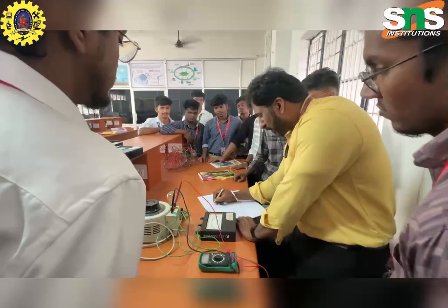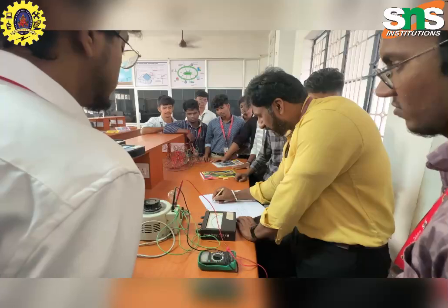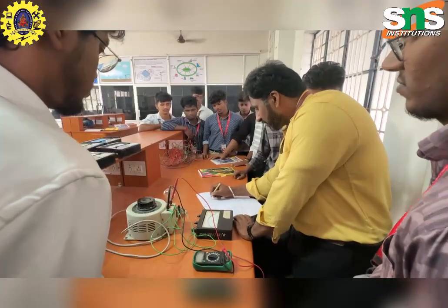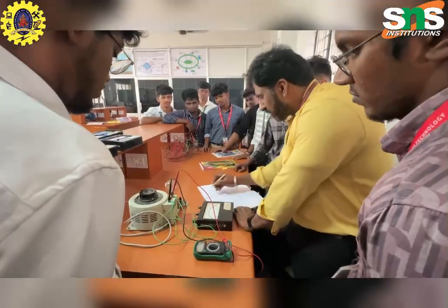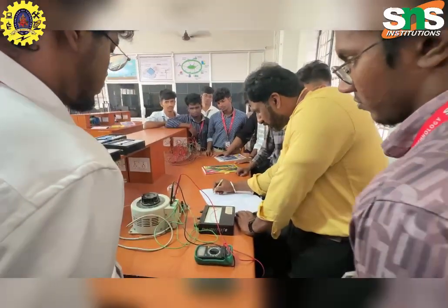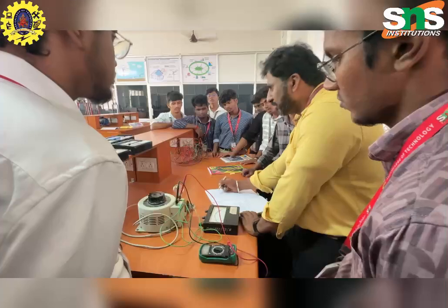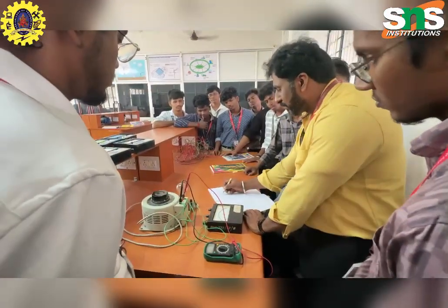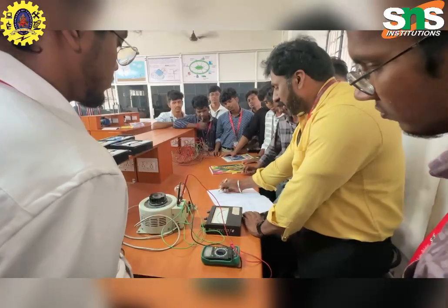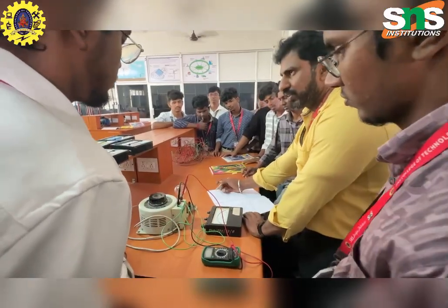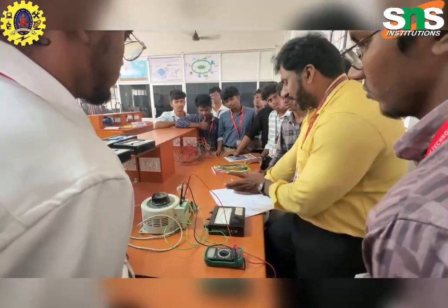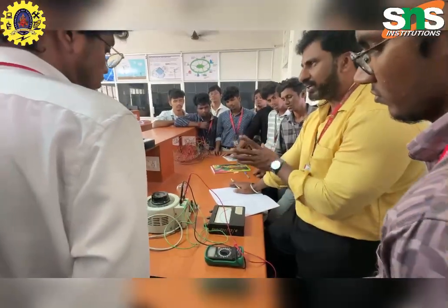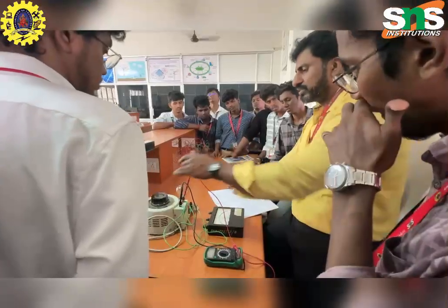So I have a supply voltage, and directly connected to it is one voltmeter. This voltmeter will be the standard one, a multimeter. The next voltmeter is the test meter, or measuring meter. When we switch on the supply, the standard meter will show one value and the test meter will show another value. So we have different values. When directly connected to the supply, we can take only one reading, but we need more than 5 readings. That's why we are using a variac.